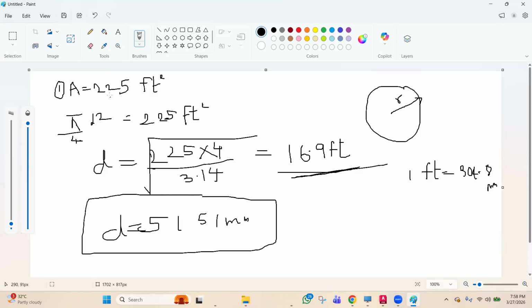We have taken the area as 225 square feet for a light hazard hotel building. Since it's a hotel building, and it's a circular coverage, pi by 4 d square will be the area. So pi by 4 d square is equal to 225 square feet, and d is equal to under root of 225 multiplied by 4 divided by 3.14, which is our pi value. So we get 16.9 feet as d. But mostly we work in mm, so since 1 feet is equal to 304.8 mm, if you convert this feet into mm, the d value comes to 5151 mm. Clear?